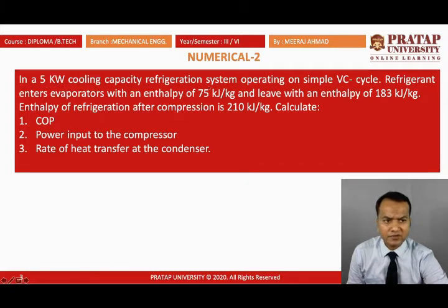The refrigerant enters the evaporator with an enthalpy of 75 kJ per kg, and leaves with an enthalpy of 183 kJ per kg.